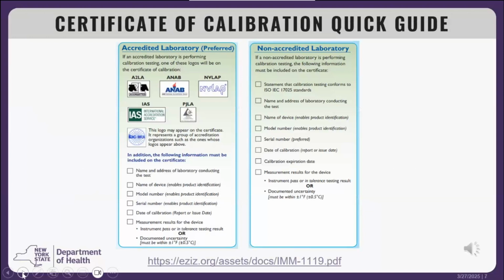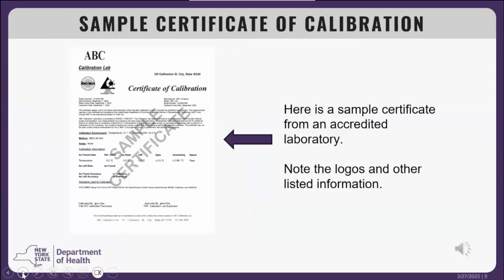Here are some cheat sheets to help determine if a calibration certificate is acceptable. Accredited laboratories will have one of the logos seen on the left, in addition to the items listed below. Refer to the list of items on the right to determine if calibration from a non-accredited laboratory is acceptable. This slide displays a sample calibration certificate from an accredited laboratory. Note the logos and other listed information.